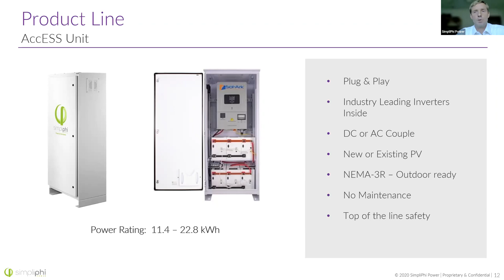The beauty of this is that it's really plug and play. You can install it outdoors or indoors. About the only thing you need to do is make the final electrical connections to the system, put in your disconnect switch, and hook it up. So if you're looking for fast, quick installations to be in and out of the customer's house and move on to the next job, those AccESS cabinets are a good option.